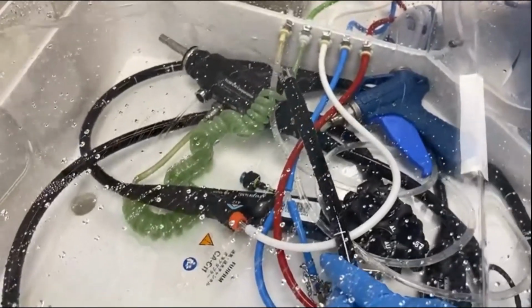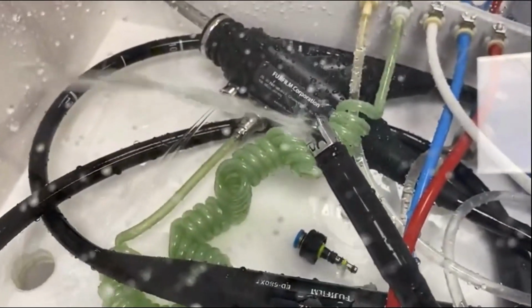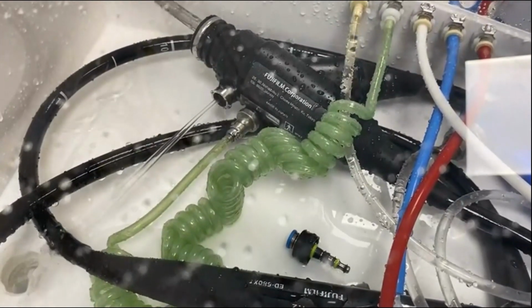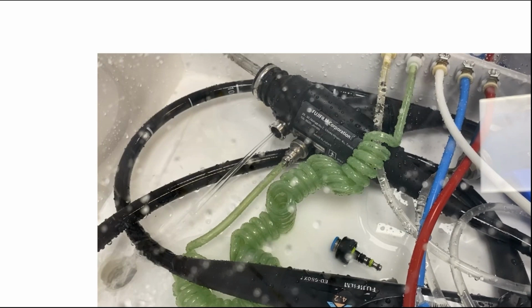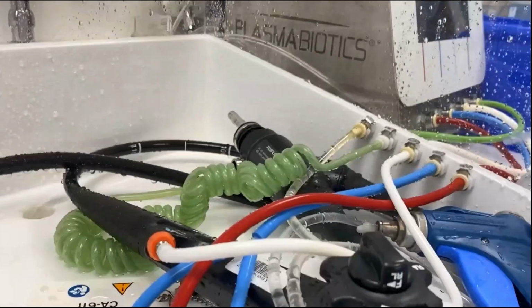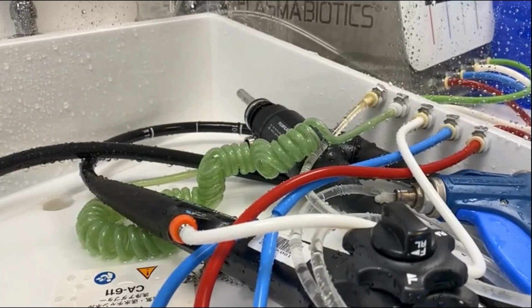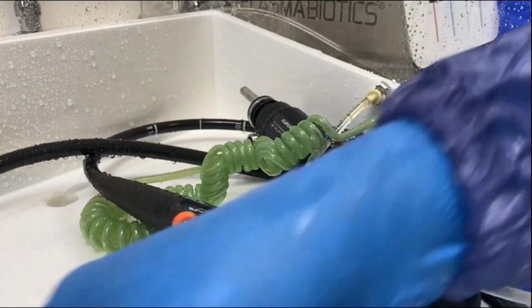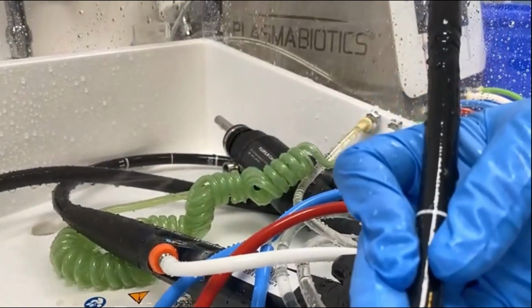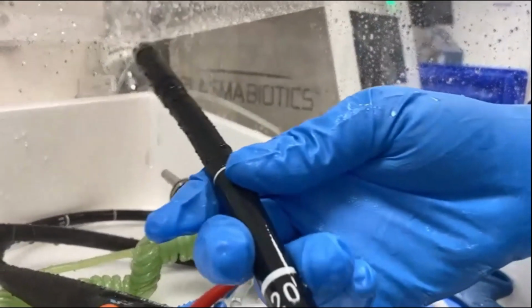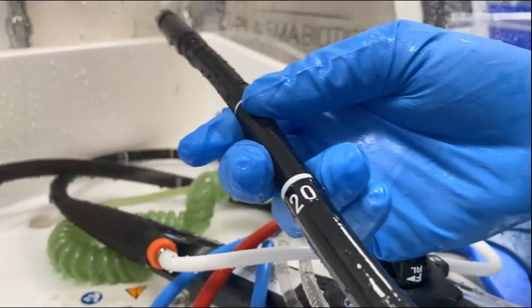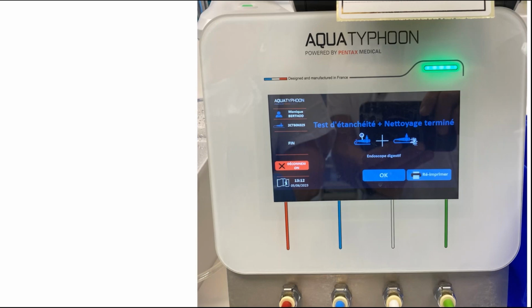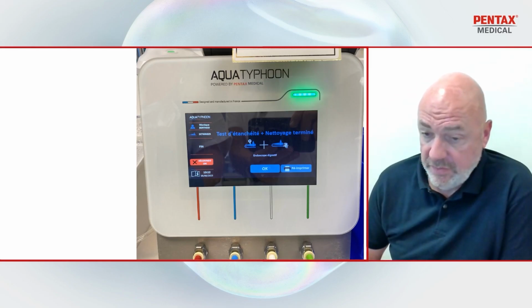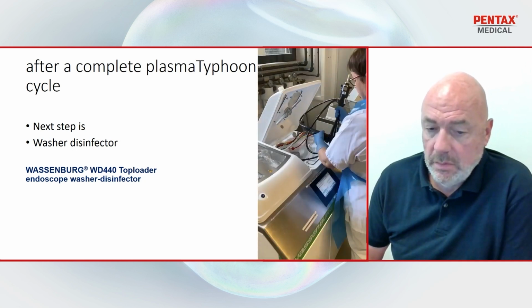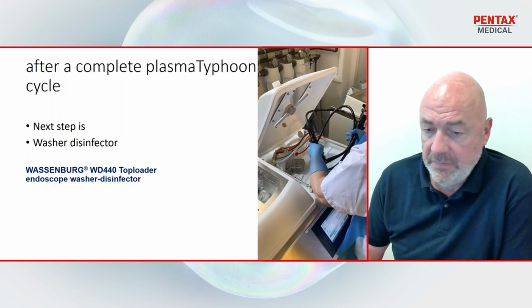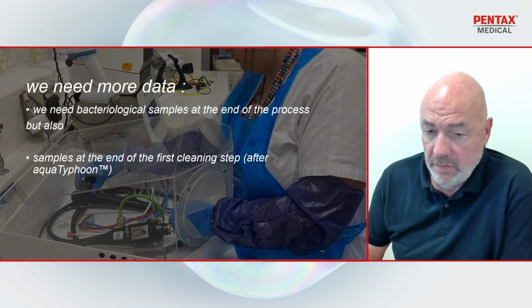You can see the water jet at the outlet of the scope, on the operative channel, on the water channel, on the air channel. You can see I put the camera inside the Aqua Box. Dangerous for my phone, but you can see the aqua jet. And finally, the cleansing is finished. So you have to put the endoscope in an endoscope washer disinfector to make the disinfection.